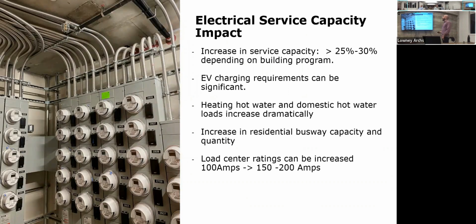Last bit, the impact on electrical service capacity. So we're electrifying our buildings, great. But because we're adding more electric-based equipment, your electrical service capacity now needs to be larger than what you are used to seeing. On average, it's around 25 to 30% larger, depending on your building program, it will change, of course. EV charging requirements can be significant. They have a big impact on the electrical loads. Heating hot water, domestic hot water loads increase dramatically.